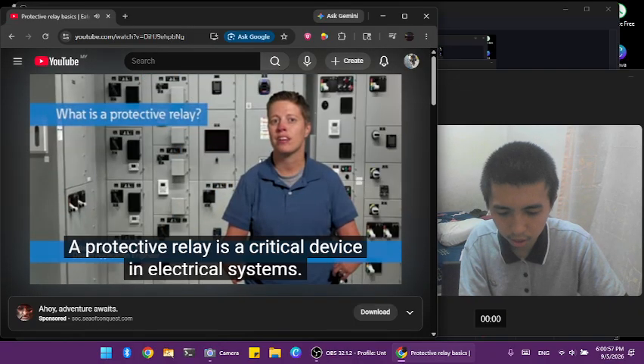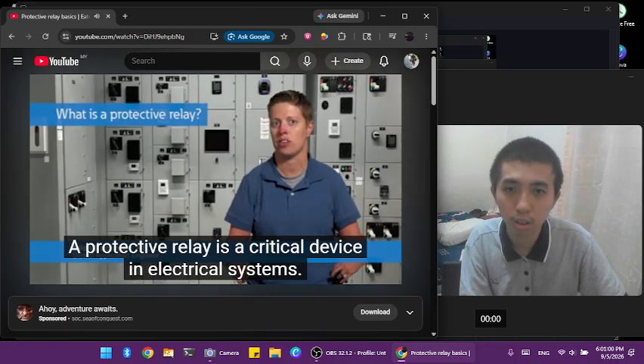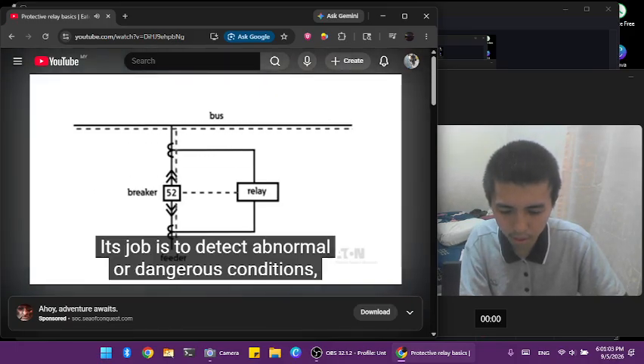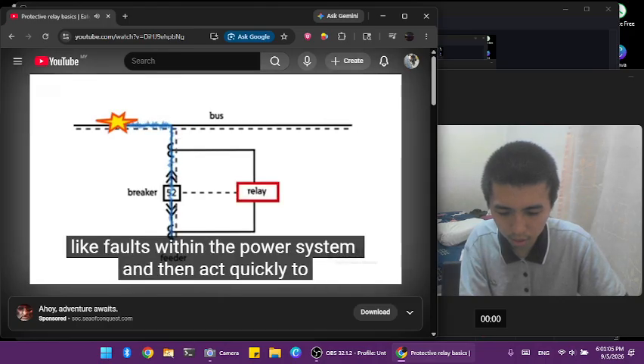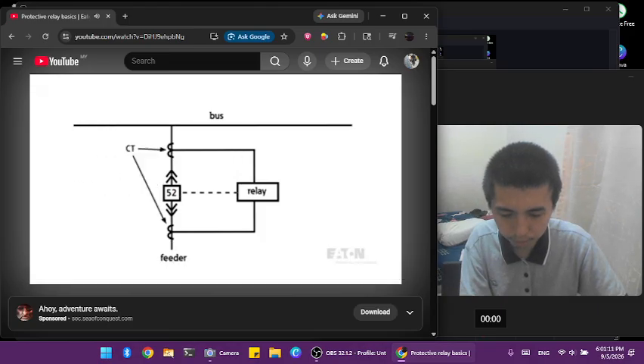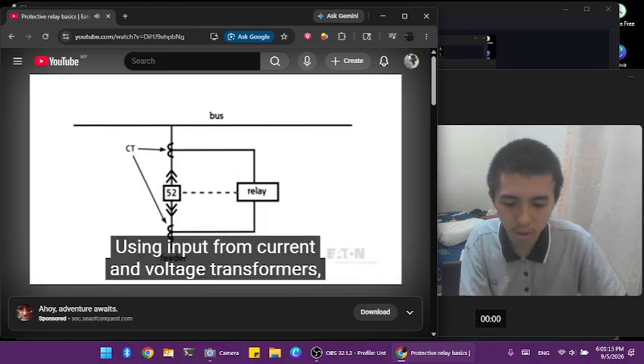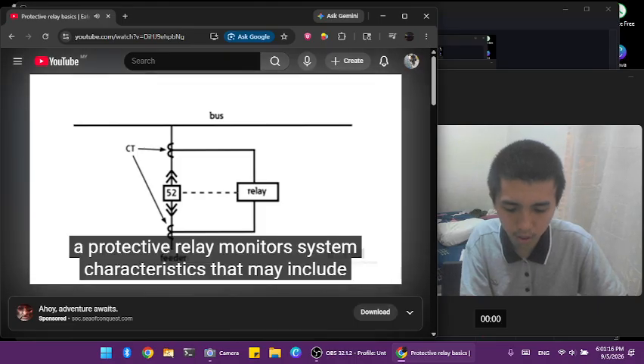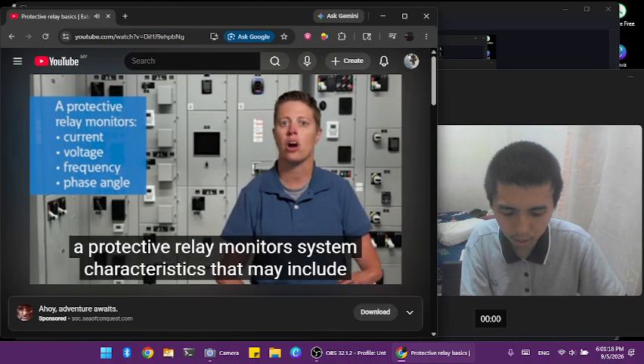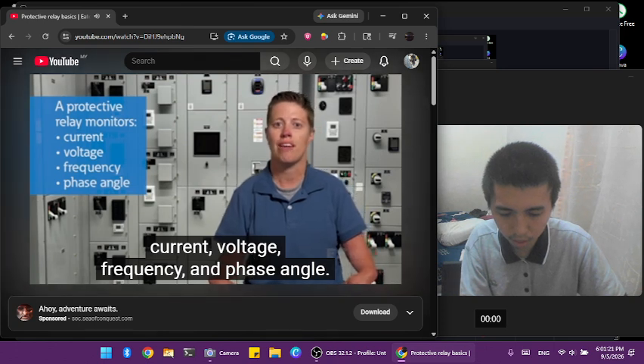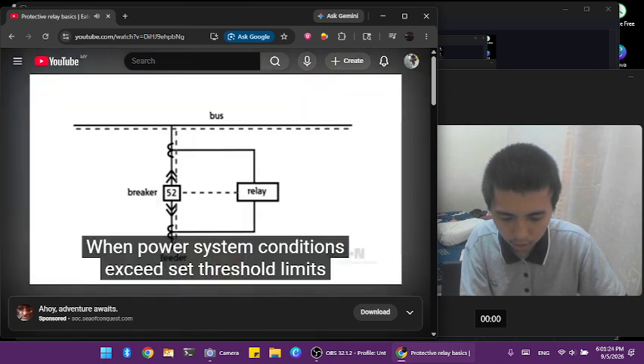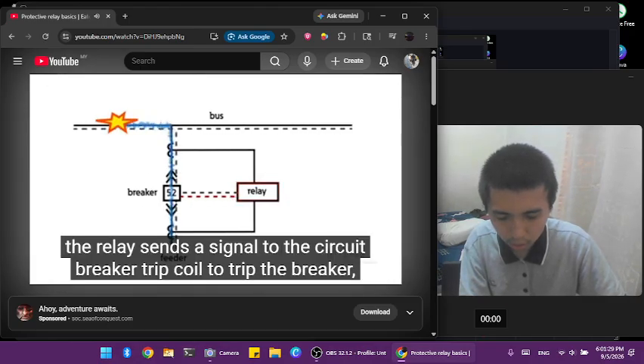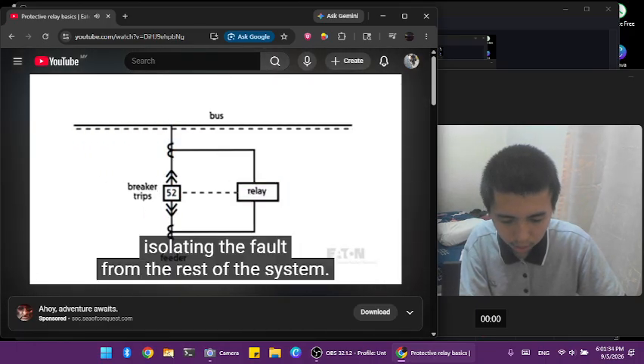A protective relay is a critical device in electrical systems. Its job is to detect abnormal or dangerous conditions, like faults, within the power system and then act quickly to clear the fault from the system. Using input from current and voltage transformers, a protective relay monitors system characteristics that may include current, voltage, frequency, and phase angle. When power system conditions exceed set threshold limits, the relay sends a signal to the circuit breaker trip coil to trip the breaker, isolating the fault from the rest of the system.